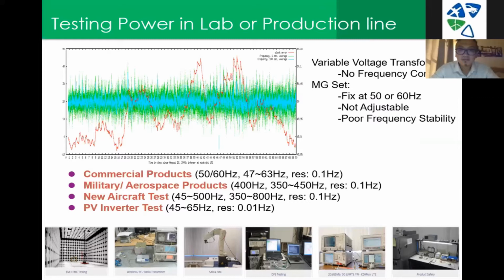For example, in Mexico I believe it's 60 hertz, but usually in the standard you cannot just test at 60 hertz, because the standard may ask you to test from 47 to 63 hertz, or up to 10% more or less. They want you to test in different power conditions. For military applications, they may ask you to test at 400 hertz, or 350 to 450 hertz.